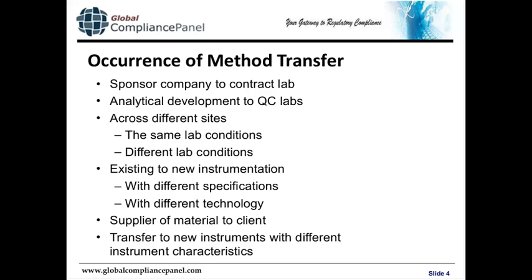If the new instrument has different specifications or different technology, a method transfer process should be used. Also, if you have a good supplier of reference material, they may provide the method for cross-checking the material, and this method also has to be formally transferred to new instruments with different instrument characteristics. And if a sponsor company has a validated method and wants to use a contract lab to run it without paying to develop a new one, they can use the same transfer process.